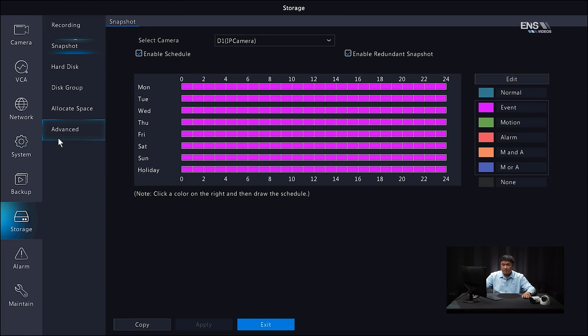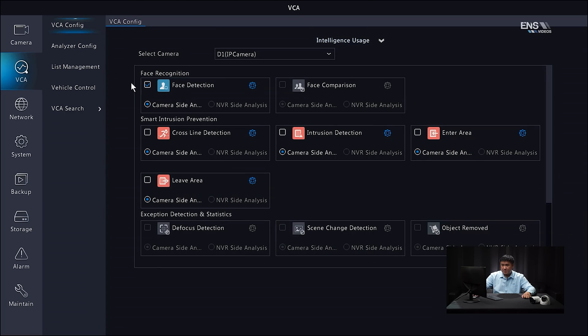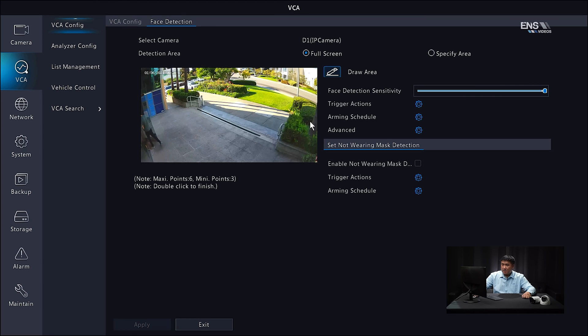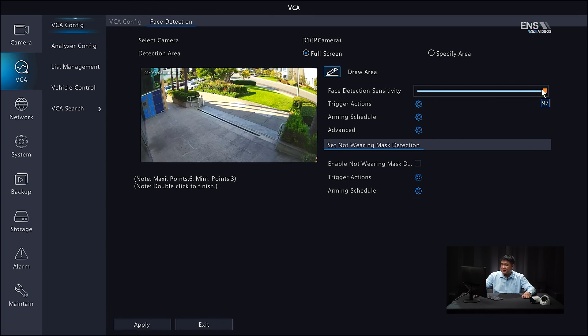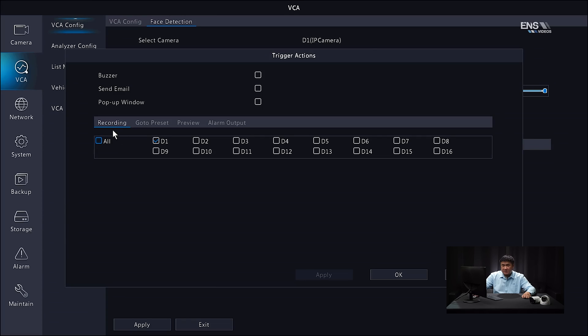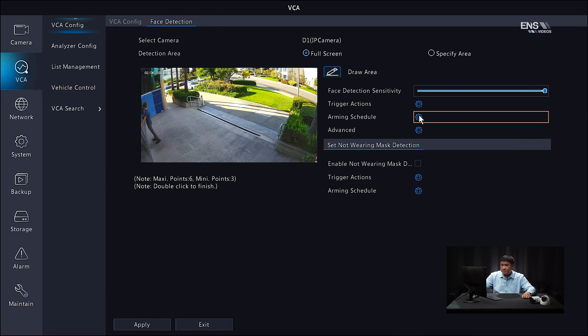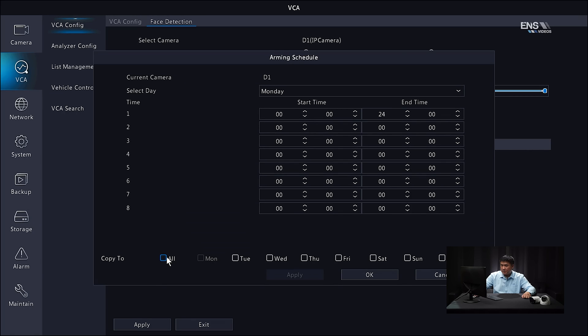Next, go to the Main Menu's VCA features and enable Face Detection. Under VCA Configuration, check the Face Detection checkbox and click the gear icon. Under Detection Area, select either full screen or specify an area — in this example we'll use full screen. Set the sensitivity level; in this example it's set to highest. Under Trigger Actions, make sure recording is enabled for the specific camera (D1 in this example). Click OK. Under Arming Schedule, select all the days you want and click Apply.